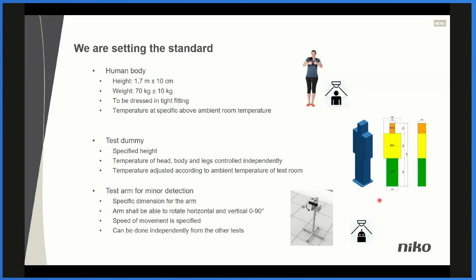And as you can see, there are also very specific requirements for the size of it. And the temperature has to be adjusted according to the ambient temperature of the test room as well. And if you want to, let's say, measure your detector at a height of 20 meters or something like that, it's not necessary to find a room that fits that. Then you scale down your dummy so that you have the possibility to test it in that way instead.